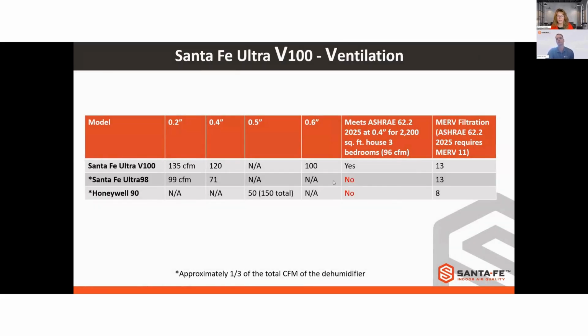So what does this look like? I took the current ASHRAE 62.2, which the most current one is 2025, at 0.4 inches of static for a 2,200 square foot home with 3 bedrooms. And I took our most current Ultra V100, the Santa Fe Ultra 98, and then the unit that has the same features as ours, but they have that 6-inch, comparable to the Ultra 98, the Honeywell 90. And this is data off of their newest models here. And what we need in order to meet this ASHRAE calculation is 96 CFM.